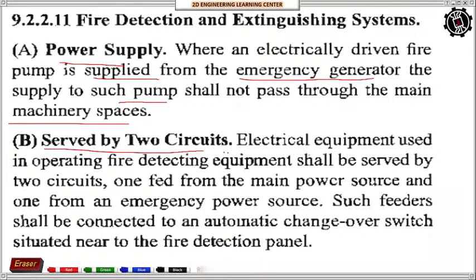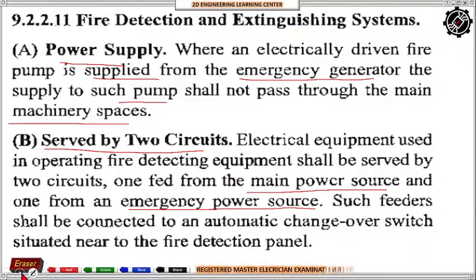Served by two circuits, so electrical equipment used for fire detecting equipment shall be served by two circuits. So yung isa is from the main power source and one is the emergency power. Para in case of emergency, hindi pa rin mawala yung power for our fire detection and extinguishing system, no? Katulad pa rin yan sa building, no? So yung ating FDAS, including the sprinkler system, must have two supply, para doon sa main at yung doon sa emergency system.